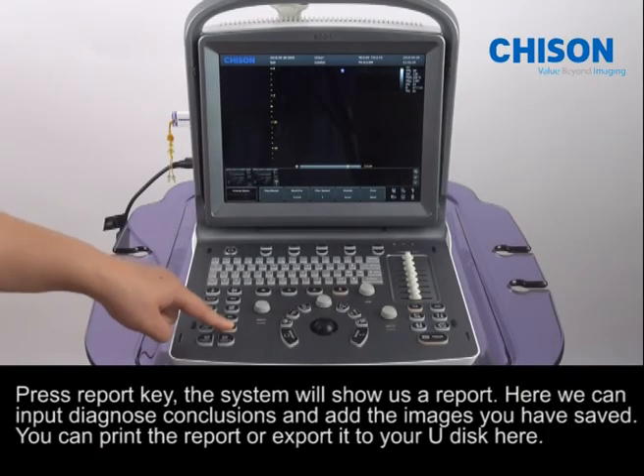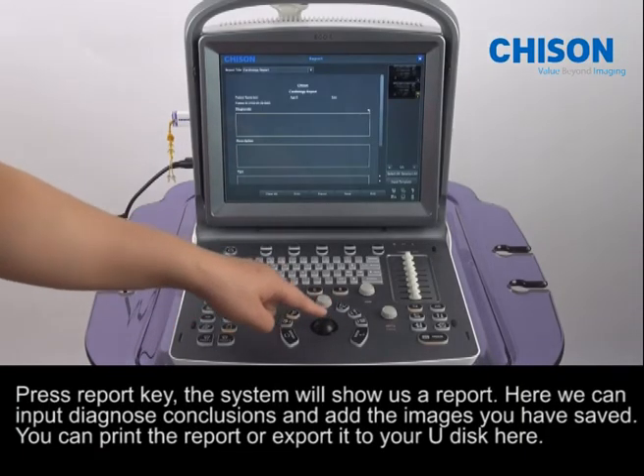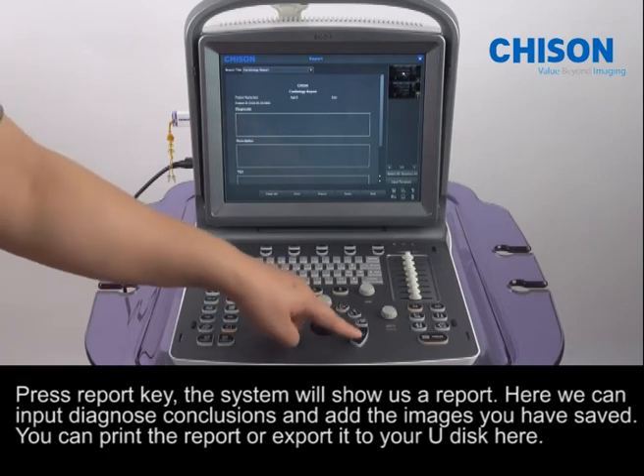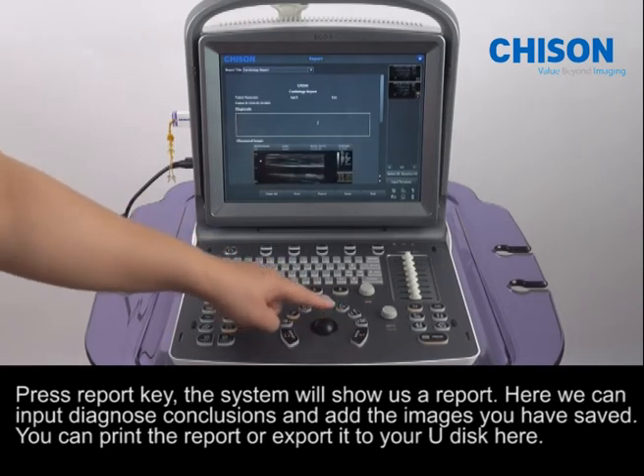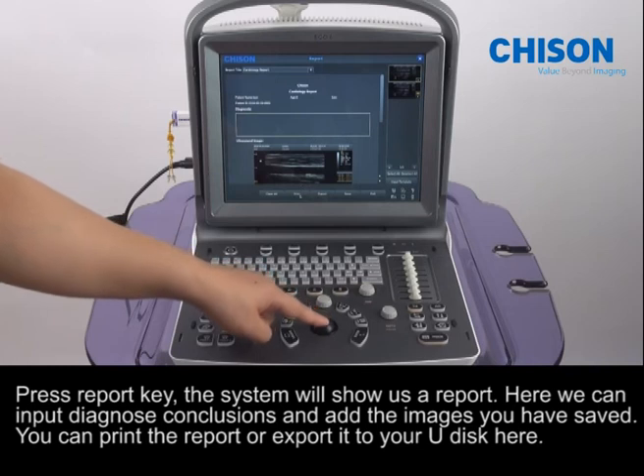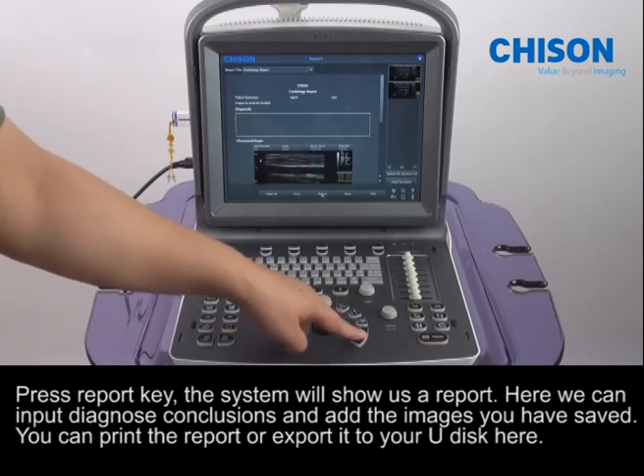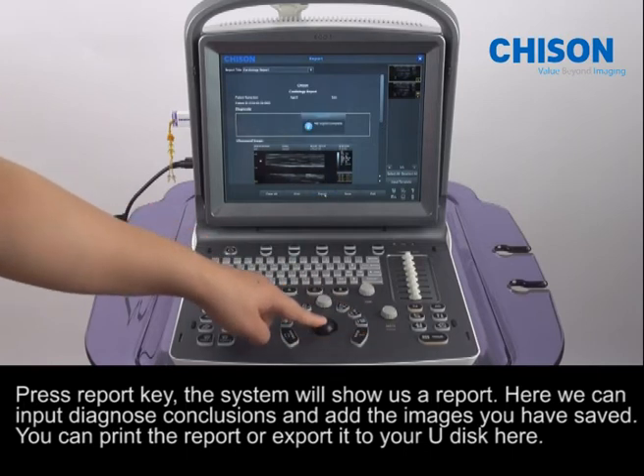Press Report key. The system will show us a report. Here we can input diagnose conclusions and add the images you have saved. You can print the report or export it to your U-disk here.